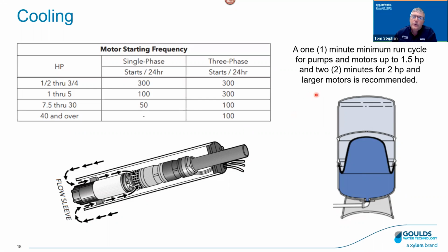The other thing that has to do with cooling, in our typical water systems, is the tank. So we can see here the general rule of thumb for sizing our tank. And this is a minimum, by the way. I would say even recommended would be double this, but minimum would be a 1 minute minimum run cycle time for pumps and motors up to 1.5 horsepower and 2 minutes for 2 horsepower and larger. So that's a pretty standard rule of thumb. Again, that's minimum. Recommended would be double that.